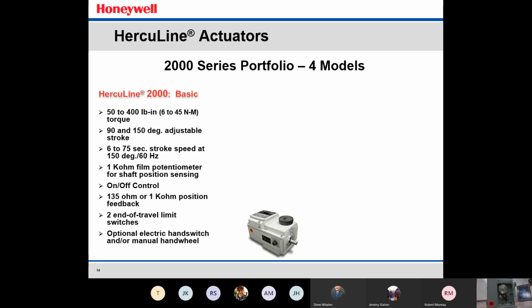It has a 1K ohm film potentiometer for shaft positioning. Now this is a contact potentiometer. This is not a non-contact, so you will get a 0 to 1,000 ohm feedback. You can either put a small voltage across that feedback to give you a linear voltage feedback, or you can just use the 1,000 ohms to bring back into a position proportional controller. It is a thin film pot though, so it's not a wire wound resistance. So it offers a little bit better repeatability and also a little bit less maintenance headaches.